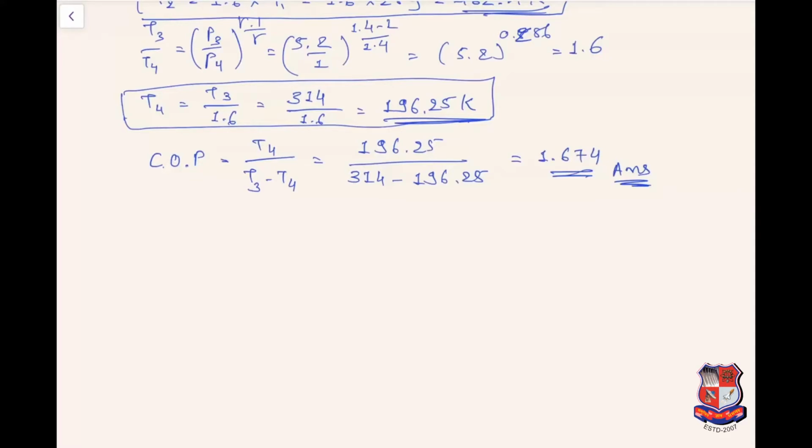So that is first what we need to find out. Second one is the quantity of air in circulation per minute. For that, the mass of air needs to be found out. So MA, that is mass of air. Now for that we need to first find out the heat that needs to be extracted from the machine. Whatever heat needs to be extracted from the machine is QA.